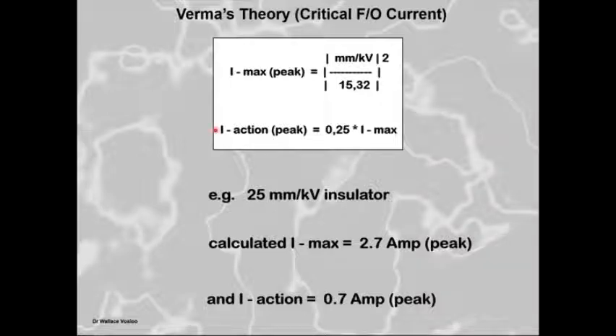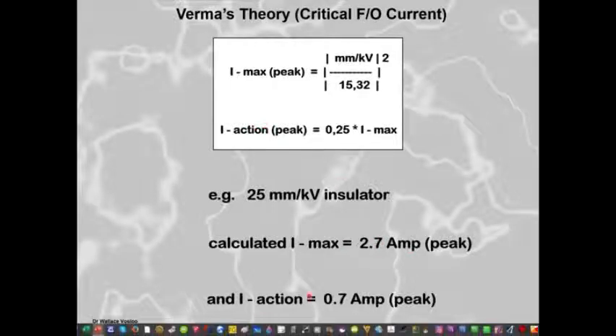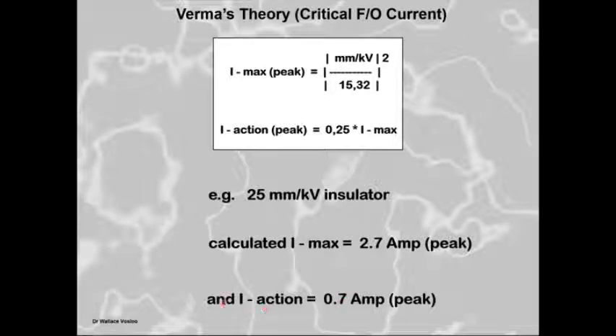And then myself and Dr. Holzhausen, especially Dr. Holzhausen, came up with and said, you better take action when the peak value is a quarter of that value. And so when you're monitoring the leakage current in your network, and you've got a 25 millimeters per kV insulator, you will get flashover at 2,7 amps. If you measure 2,7 amps on that, it's already too late. It's already flashed. You need to take action when it becomes 0.7 amps, 700 milliamps. Well, to be quite honest, if you were walking underneath those insulators with 700 milliamp levels of leakage current on it, you will have to change your underpants a few times before you reach the end of the line. But this is the theory from Verma and Holzhausen and myself.